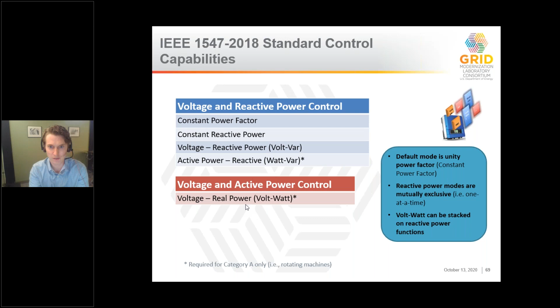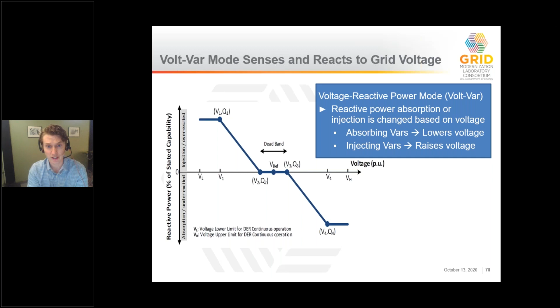What we're looking at on the screen is the characteristic curve of the Volt-VAR function. What we have on the vertical axis here is reactive power that's either being injected or consumed by the DER. And on the x-axis here, we have the voltage of the system. So for higher voltages, the DER is going to consume reactive power, pull it from the distribution system, and that has that sort of cancellation effect that we discussed by opposing the direction of the active power flow.